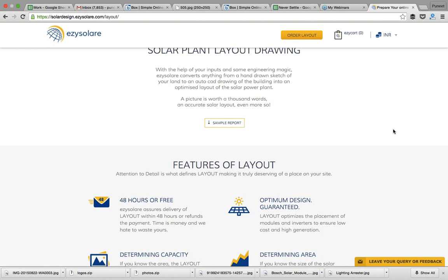Do you require lightning arresters, SCADA, and firefighting equipment for a rooftop system? SCADA is slightly different, but lightning arresters and firefighting equipment are more a matter of health, safety, and environment, so you won't want to compromise there. Imagine a situation where there is a fire in the system and you lose the entire system just because you didn't have a fire cylinder handy. Or imagine lightning struck and, in order to save about 20,000 rupees, you didn't put in a lightning arrestor. It's important to note that lightning arrestors are of two types: ESE type and conventional type.